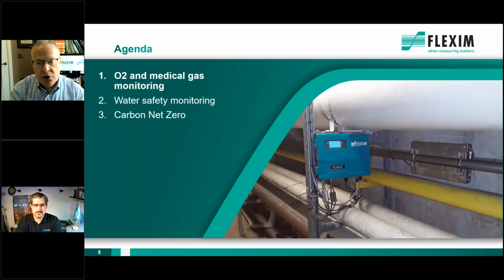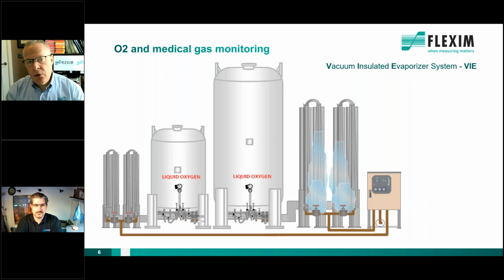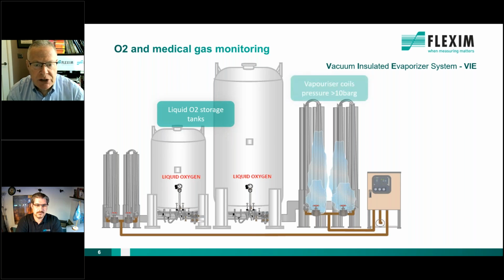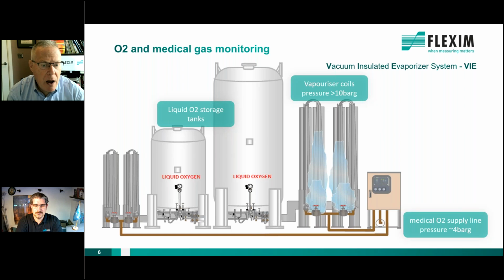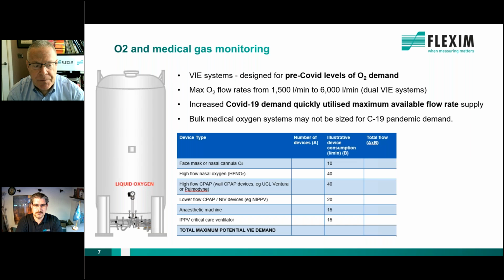Let's look at those oxygen applications. So basically, most hospitals will have a VIE, a vacuum insulated evaporator, usually one or two tanks. So you have your liquid oxygen tanks, and a vaporizer coil or two that will turn that liquid oxygen into vapor. And then we're supplying to the hospital at approximately 4 bar. Obviously there's a control panel to look after all of that.